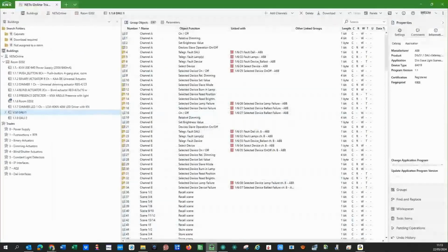So I have done this job in my DALI 1 gateway, the DGS 1.1 reference from ABB. I just configured the parameters properly to get these objects, fault DALI, LAMPS device. Some of them are not mandatory, but I did it. So these are objects number 4, 5, 6, 7, 8, 15, and 16. This is what I did.